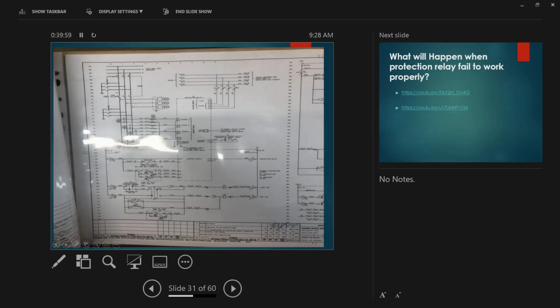That's another thing. And if this one is open here while you're doing testing, there will be an induced voltage here, high voltage. You will get an accident because the CT will produce some induced voltage if you have current flowing on the primary. So still, we suggest that we have to do proper isolation. Yeah. That's the safest one.